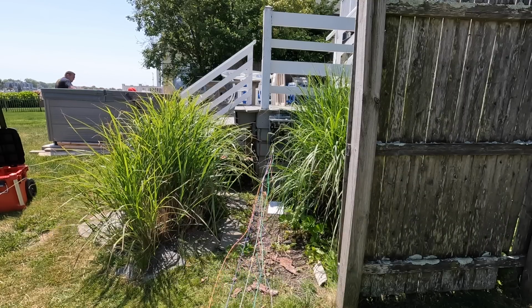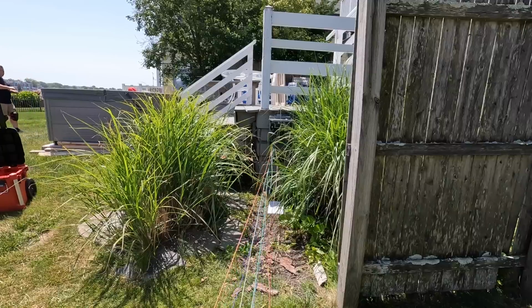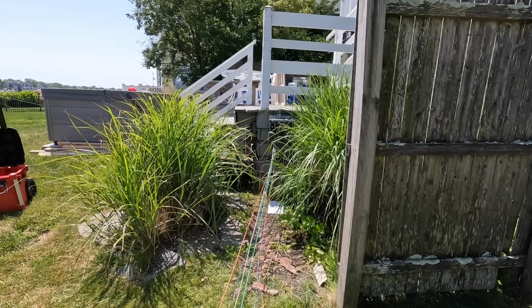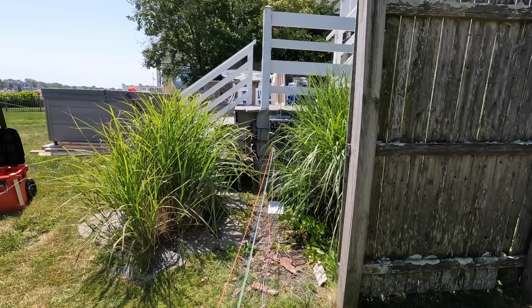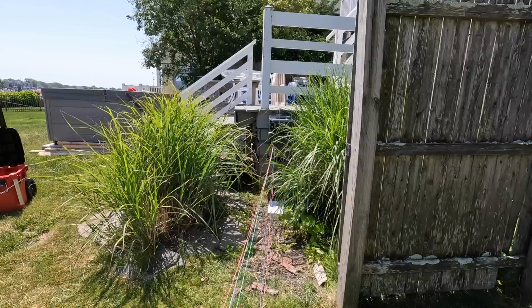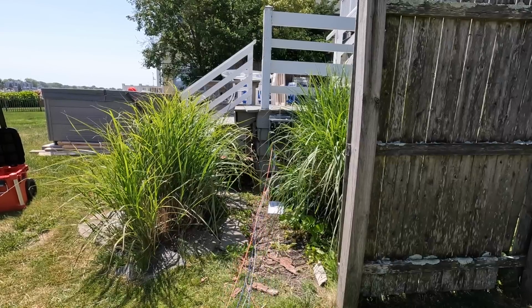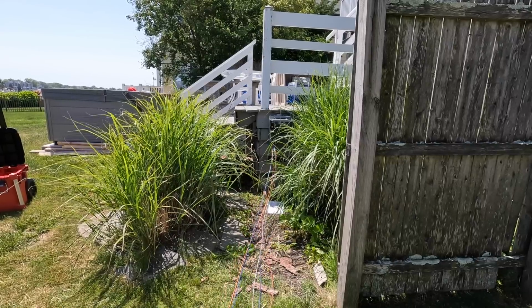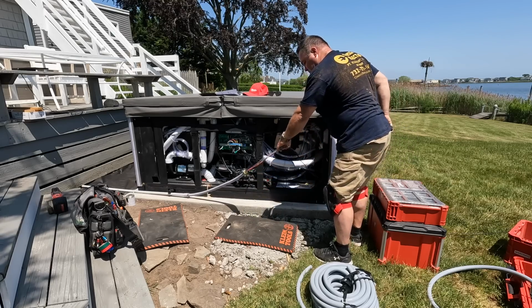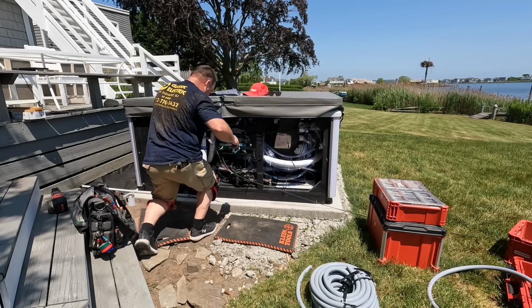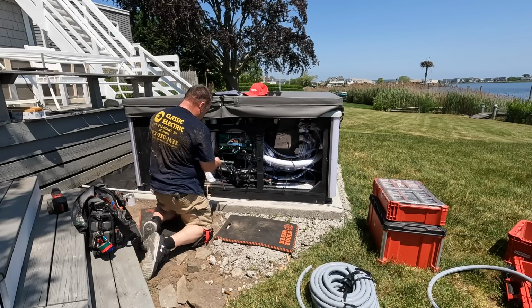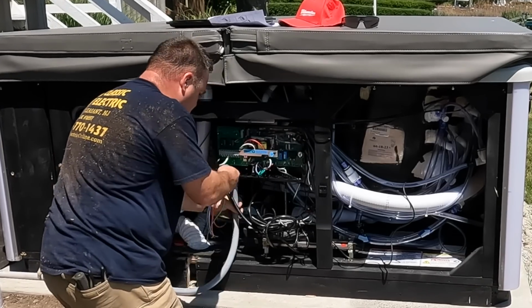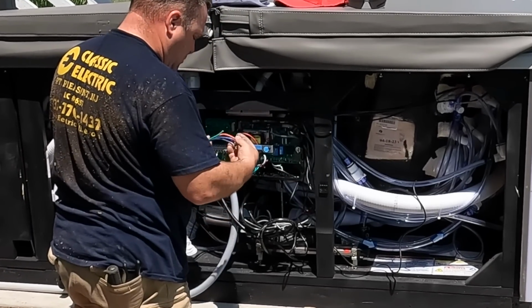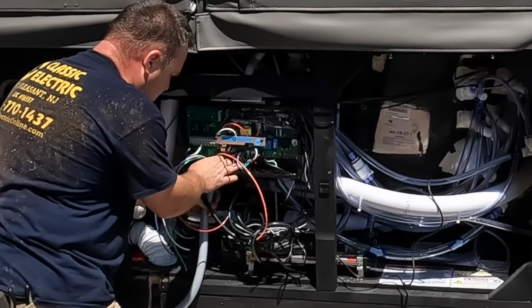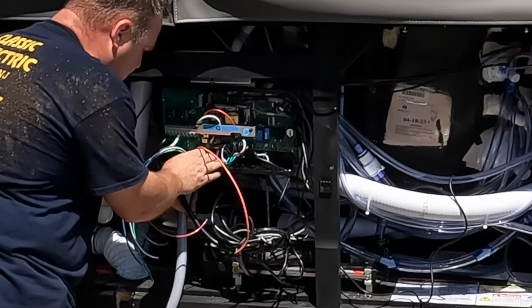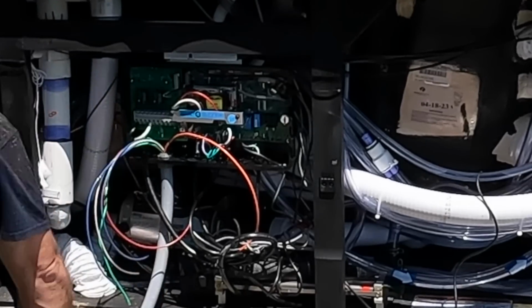And so there I am on the other side by the hot tub, pulling the conductors that are set up on a reel. I've got two number 10s, two number 12s, a neutral number 12, and a number 10 equipment grounding conductor. What's amazing about this pull is the number 10 green that I had just barely enough. And as I recall, when I pulled the feeders from this main lug panel to the other main lug panel, my neutral wire was just barely long enough at the panel. I had to extend it, but it reached out of the panel maybe about 8 inches. So that's twice on the same job where the end of the reel was a real thing, and I had just enough to do both.